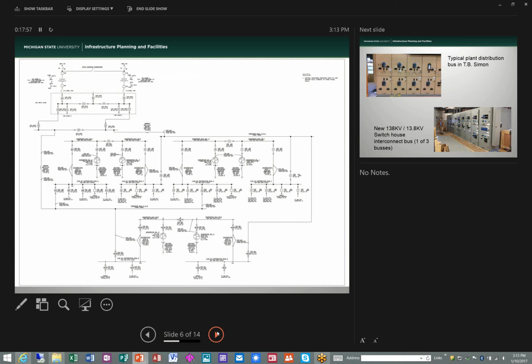That creates one of the challenges going forward, commensurate to what Bob was referring to: going forward, cooling will be electric chiller versus steam absorber due to efficiencies. We have quite a few steam absorbers at end of useful life in the near term, so a campus master cooling plan has been developed calling for about 20 megawatts worth of electric-driven chiller cooling over the next 20 years.